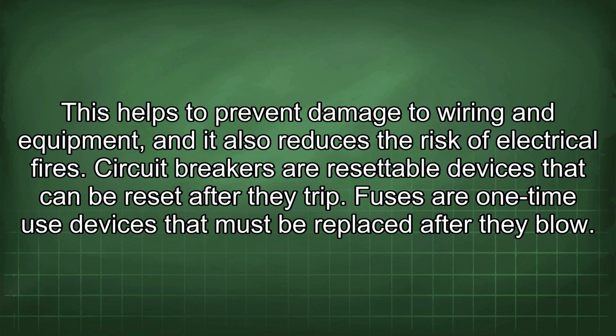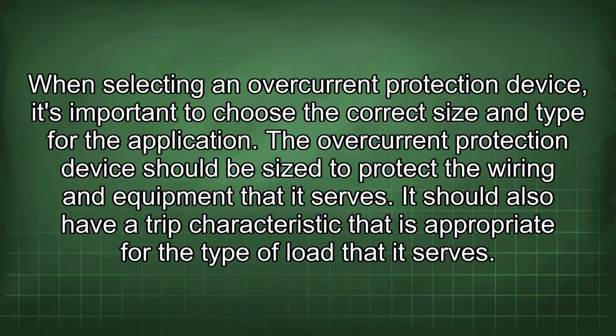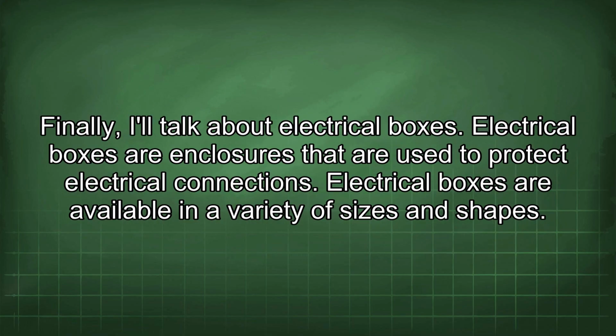Circuit breakers are resettable devices that can be reset after they trip. Fuses are one-time use devices that must be replaced after they blow. When selecting an overcurrent protection device, it's important to choose the correct size and type for the application. The overcurrent protection device should be sized to protect the wiring and equipment that it serves. It should also have a trip characteristic that is appropriate for the type of load that it serves. Finally, I'll talk about electrical boxes.